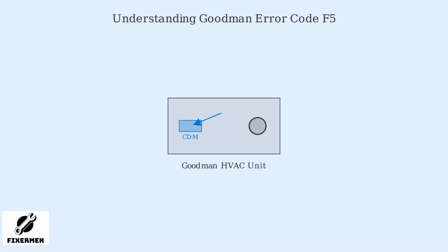Goodman error code F5 indicates a fault within the compressor drive module in Goodman HVAC systems, primarily air conditioners and heat pumps. The compressor drive module, or CDM, is a circuit board that controls the variable frequency drive for the compressor, regulating its motor speed for energy efficiency. When the module detects anomalies like overcurrent, undervoltage, or phase imbalances, it triggers the F5 error.